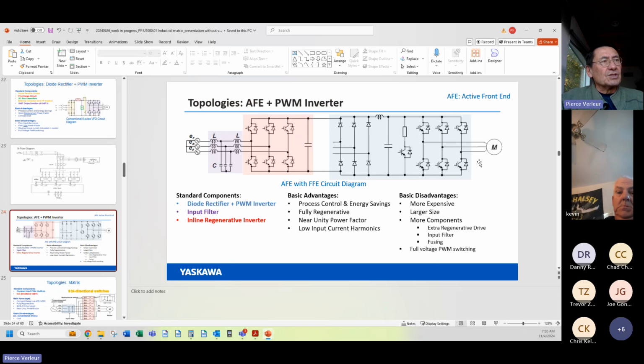You have an inverter section here with its transistors and effective diode bridge. You have transistors and effective diode bridge facing the power line. You can now shape the waveform going back and forth. This is actually a regenerative drive. You can power the motor, passing power from the line to the motor. When the motor regenerates, such as a hoist going down instead of up, the load drives the motor and it becomes an alternator. That power is rectified through this diode bridge here back to DC on the DC bus, and we now can push that power back to the line.